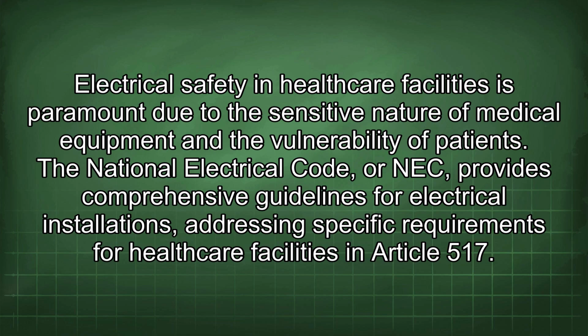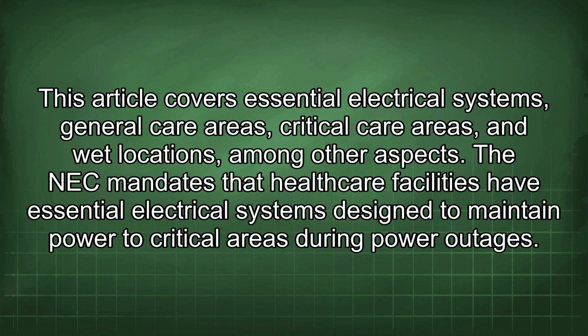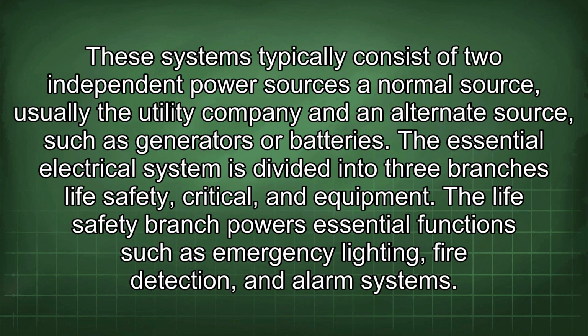Electrical safety in healthcare facilities is paramount due to the sensitive nature of medical equipment and the vulnerability of patients. The National Electrical Code, or NEC, provides comprehensive guidelines for electrical installations, addressing specific requirements for healthcare facilities in Article 517. This article covers essential electrical systems, general care areas, critical care areas, and wet locations, among other aspects. The NEC mandates that healthcare facilities have essential electrical systems designed to maintain power to critical areas during power outages. These systems typically consist of two independent power sources: a normal source, usually the utility company, and an alternate source, such as generators or batteries.